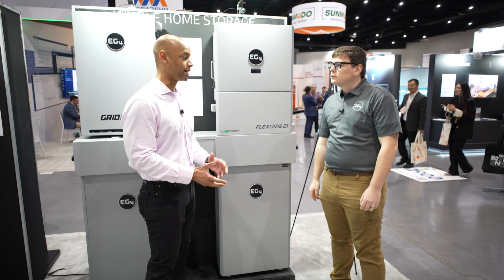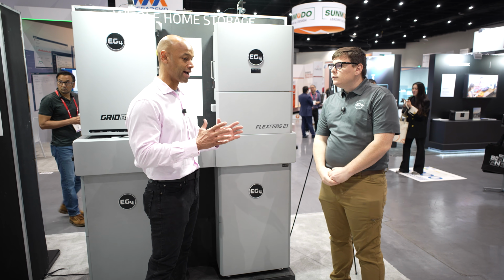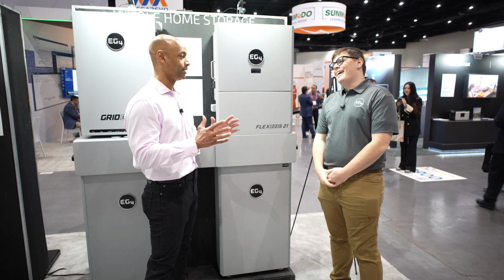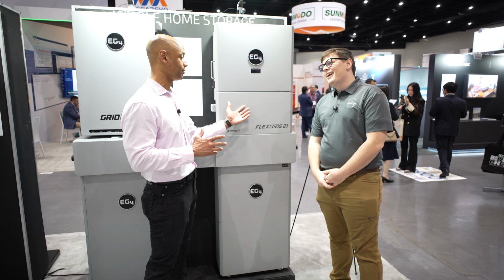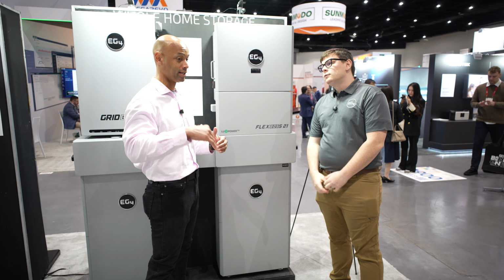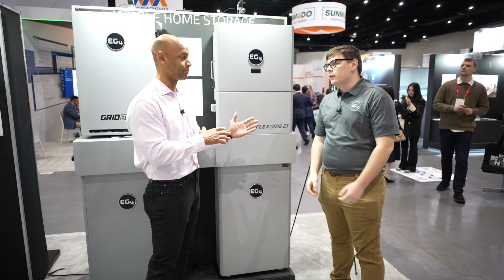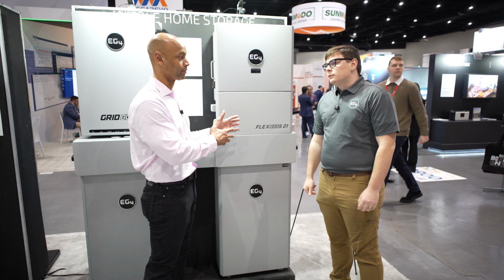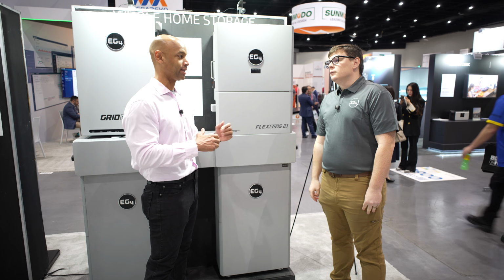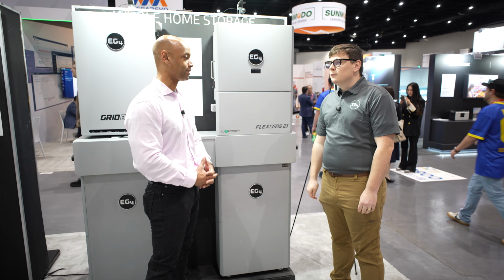Makes a lot of sense. As a former electrician too, you have to have all this high amperage switchgear to be able to bypass the inverter in case it fails and you have to swap it out. You need a way to bypass the house back onto utility power while you do your service and repairs. A lot of times all that switching, wire, and conduit adds up, like you said.